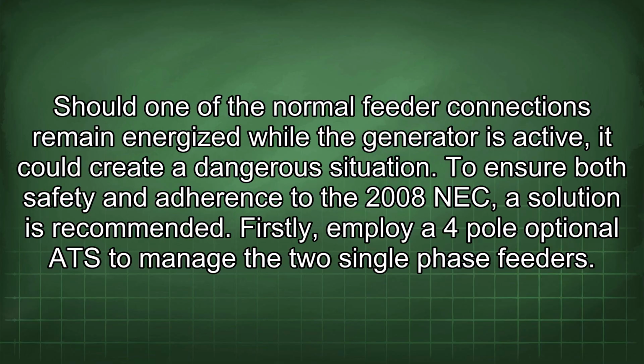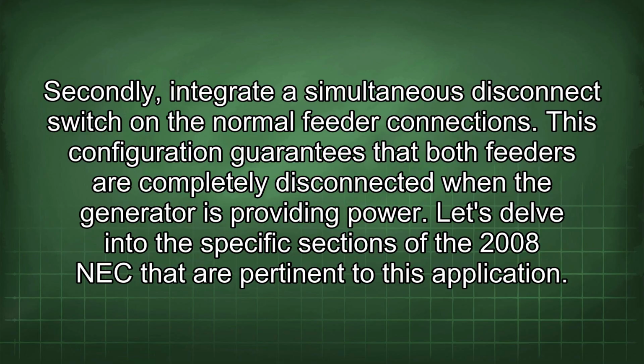To ensure both safety and adherence to the 2008 NEC, a solution is recommended. Firstly, employ a 4-pole optional ATS to manage the two single-phase feeders. Secondly, integrate a simultaneous disconnect switch on the normal feeder connections. This configuration guarantees that both feeders are completely disconnected when the generator is providing power. Let's delve into the specific sections of the 2008 NEC that are pertinent to this application.